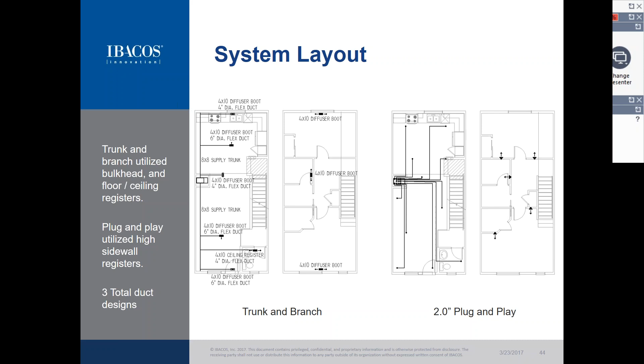Something to point out also: the 2.5-inch PVC simply wasn't flexible enough to easily install within the floor cavity. It would have needed to bend much more to fit, so we actually had to install that ductwork in the bulkhead as well. We'll see how the numbers played out — but despite that, the 2.5-inch ductwork still had much less installation time than the traditional trunk and branch system.